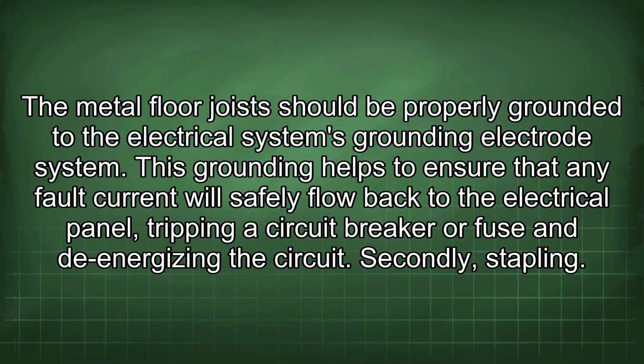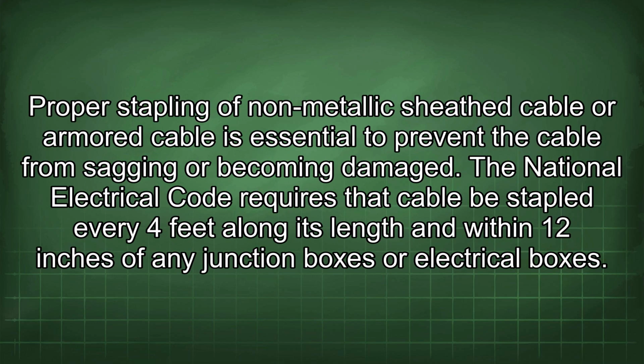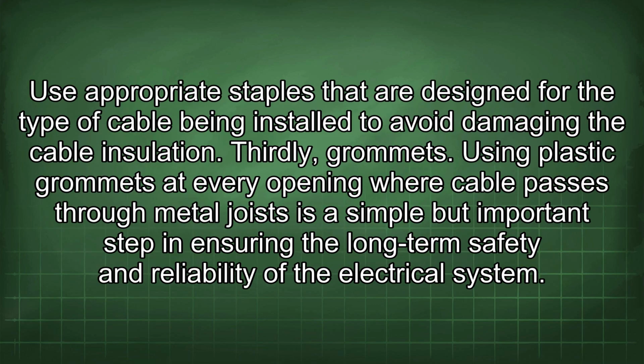Secondly, stapling. Proper stapling of non-metallic sheathed cable or armored cable is essential to prevent the cable from sagging or becoming damaged. The National Electrical Code requires that cable be stapled every 4 feet along its length and within 12 inches of any junction boxes or electrical boxes. Use appropriate staples that are designed for the type of cable being installed to avoid damaging the cable insulation.